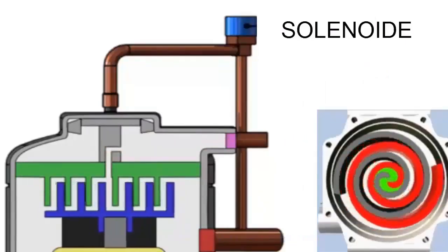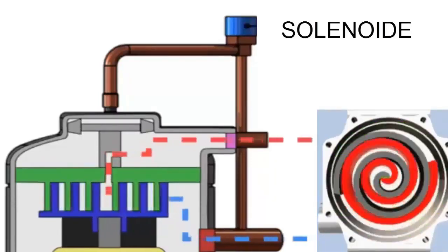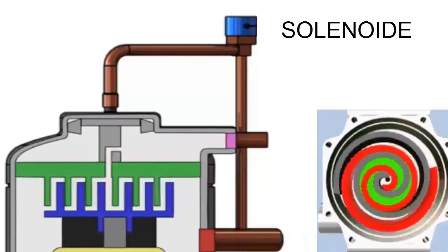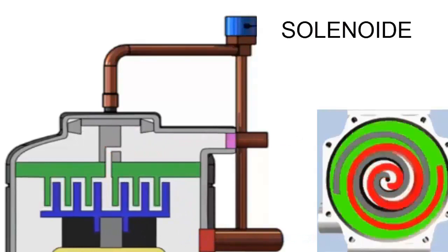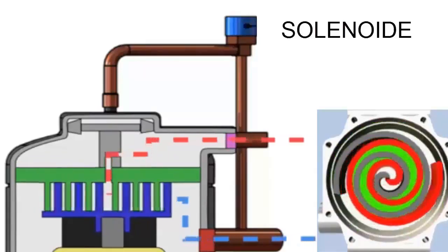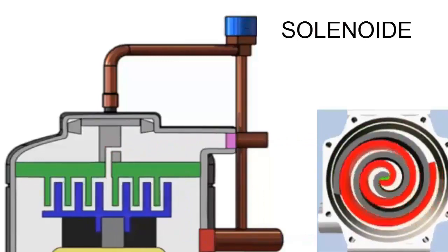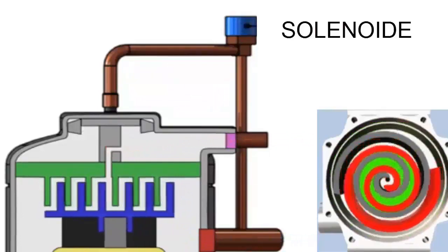Let's start by saying that the digital compressor is a scroll-type compressor that can regulate its cooling capacity by separating the compression scrolls with the use of a solenoid, thus generating considerable energy savings, especially on those occasions where there are variable cooling loads, for example, in air conditioners that work day and night or that are installed in premises where the number of occupants changes.